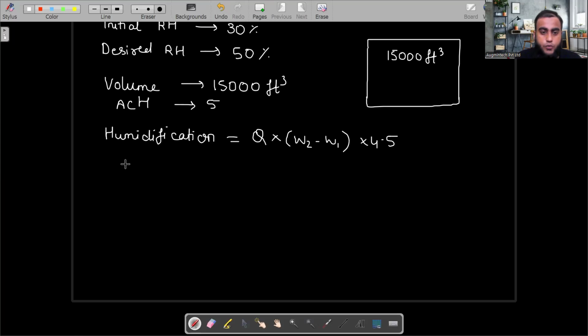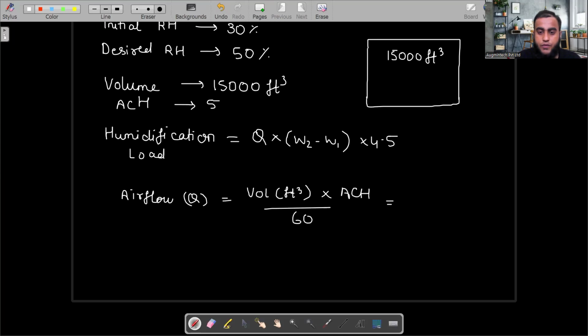Now, the formula to calculate the humidification load is given here clearly. First, I will show you how to calculate the airflow rate. For that, what is the formula in CFM? Volume of that space in cubic feet into the ACH value, air changes per hour, divided by 60. The volume of our space is 15,000 cubic feet, ACH we have taken 5, then 60. Just open the calculator and let me know the value. Okay, so the airflow value which we have got, the Q value, is 1250.